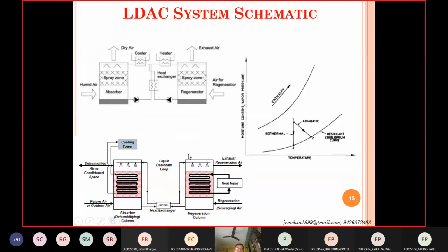So this is a liquid desiccant based cooling system, and in this system, as it was shown in the schematic previously, there are two parts of it. One is the dehumidification column, the other is the regeneration column, and it may be internally cooled, right? Though it's not a very easy idea to implement. If you can achieve that, it provides you better performance. So cooling is done while you are absorbing the moisture, and heating is done along with regeneration, that is taking out moisture from the liquid desiccant, right? Then only you can complete the cycle.